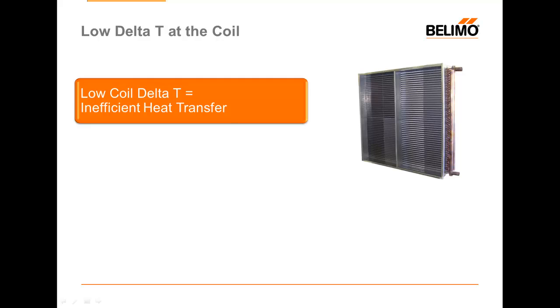When we're talking about delta T we're really talking about delta T at the coil. What we're referring to is the difference between the supply water temperature which enters the coil and the return water temperature that leaves the coil. When it's low it means that I have not exchanged a whole lot of BTUs into this space, or more accurately haven't transferred enough heat into that water.